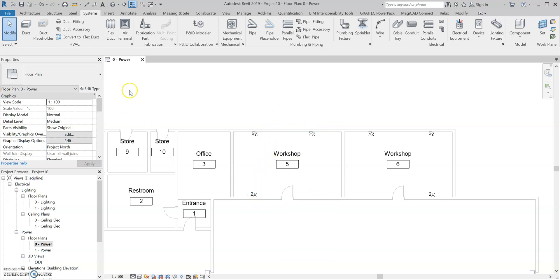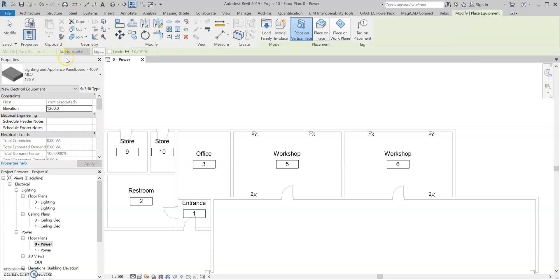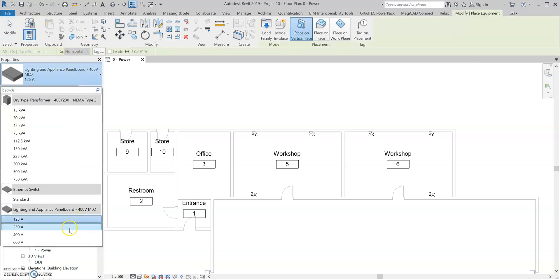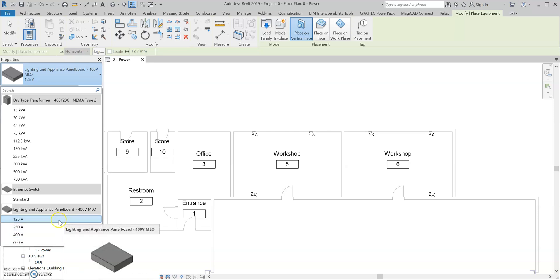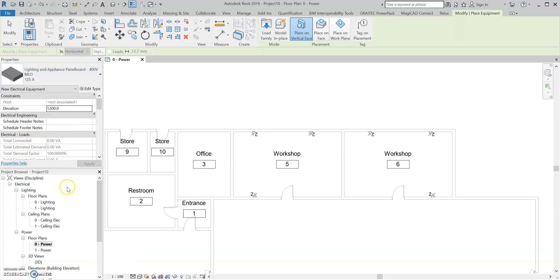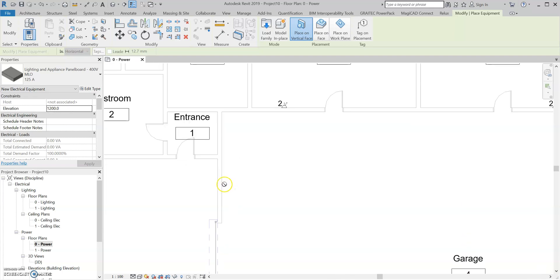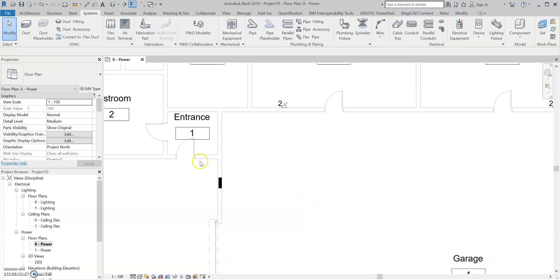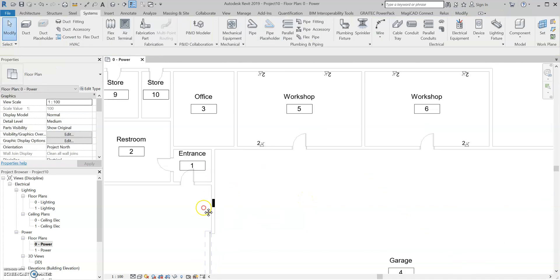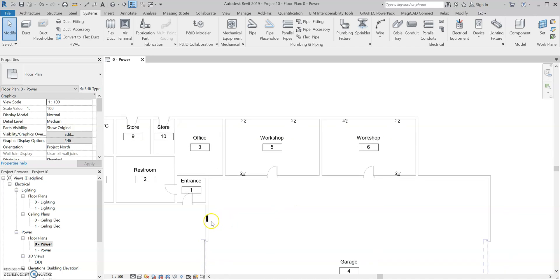We can now add in our panel board. Under Systems, I'm going to go to Electrical Equipment. In the properties, we've got a few different defaults — I'm going to go for the 125 amp panel board. I'm going to select it, and I'm just going to put it on this wall here. So now we've got a panel board in. This allows us to create our circuits — if you didn't have the panel board in and you're trying to create circuits, it just won't let you.